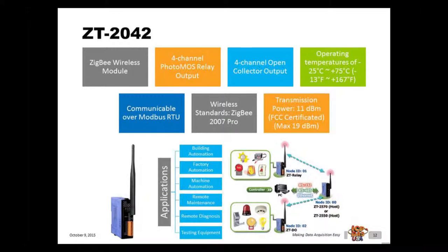The ZT2052 IOP provides external DIP and rotary switches for easy configuration, which can be used to synchronize digital signals in any environment where wiring is difficult. It is a Zigbee alliance-based digital input module that can be configured to trigger relay and digital outputs from the ZT2042 Zigbee wireless data acquisition module. The ZT2052 IOP features an embedded IO pairing function with no need for an external controller, and constantly sends status updates of the digital input channels to the remote ZT2042 to ensure that digital output channels are synchronized. Users can configure module address, protocol, checksum, ZTPID, and ZT channel settings using a combination of rotary and DIP switches.